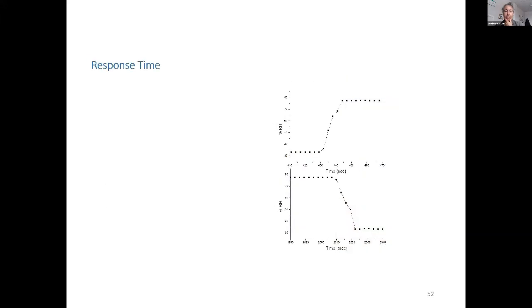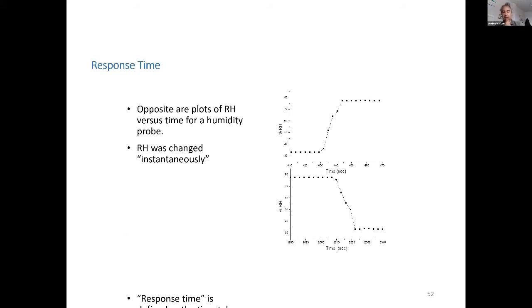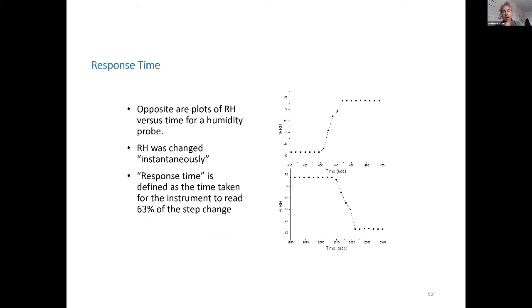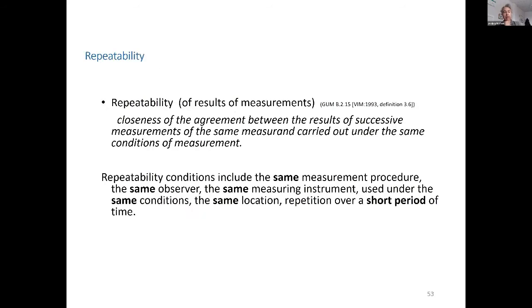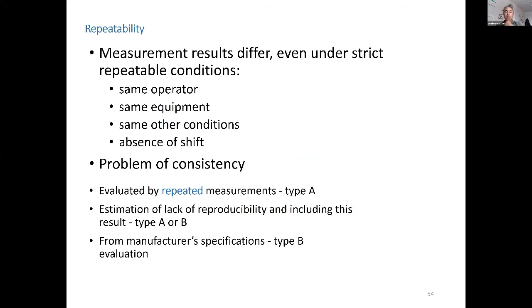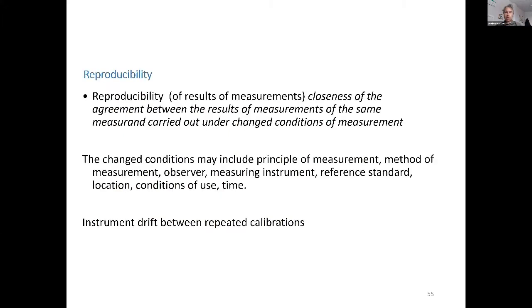The response time, if you need some dynamics in your measurement, please give a look at the response time. There are norms on how to calculate it. Repeatability gives you some information, but over a short period of time, bear this in mind. Same operator, same equipment, okay? Reproducibility, something has changed. How well is my instrument able to measure the same thing again after some time, with a new operator and with something new.